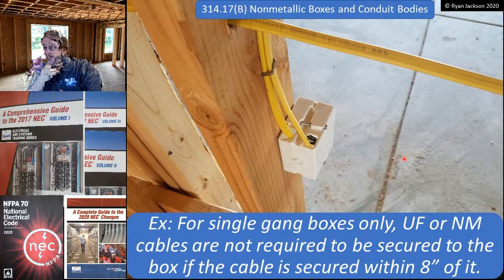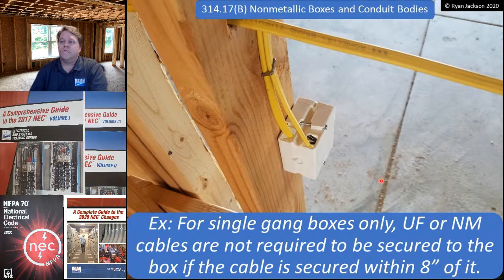Okay, so the general rule is you have to secure the cable to the box. There's an exception for single gang boxes, not two gang, not three gang, but only single gang. UF or NM cables are not required to be secured to the box if the cable is secured within 8 inches of the box. So the general rule is secure the cable within 12. However, if you don't want to secure the cable to the box and it's a single gang box and you secure it within 8 inches, then you're okay.